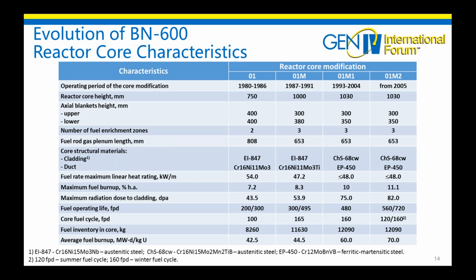Here you can see the main design characteristics of all BN-600 core modifications that were changed during its modification. You can see how the reactor core height changed, how the core structure materials changed, and how we increased our maximum fuel burnup. You can see the fuel operating life in effective days and the fuel inventory in the core. As you can see, we have 2 different fuel cycles, the summer fuel cycle and the winter fuel cycle.